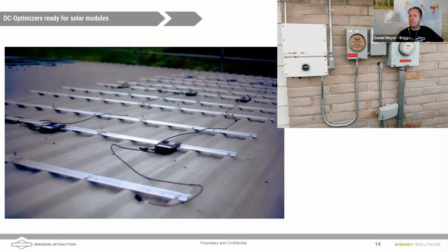And that's been a critique I've heard of DC coupled systems, is that you got high voltage DC coming down off the roof. And that was true before the requirement for rapid shutdown, where now you're required to either use optimizers, micros, or rapid shutdown devices that will disconnect on the module level that high voltage DC coming off of the roof. And these changing requirements, Daniel, are exactly why you might want to AC couple a system, right? You might have a system that has already gone through permitting, is operating completely fine, but the customer wants a battery. They want an integrated battery. They want to have backup because they're getting frequent outages.